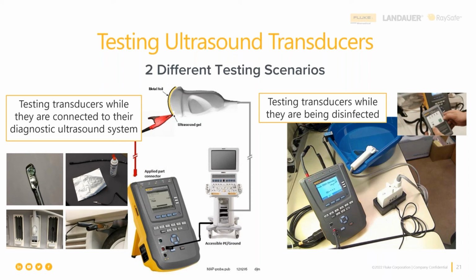Now, because the test limits are built into the ULT800, if the test fails for electrical leakage, then their job is to call a biomed, either from their own hospital biomeds or whoever's providing biomed services, and the biomed brings the regular electrical safety analyzer that they use. In this case, we're showing an ESA 615, and we're going to connect this in place of the ULT, but the ULT connectors need a little bit of a pigtail adapter here. So we use one pigtail adapter on the test lead, and we use the other pigtail adapter on the transducer adapter accessory that's appropriate for the particular brand and model of transducer that's being tested and cleaned. And that's how we run this test.